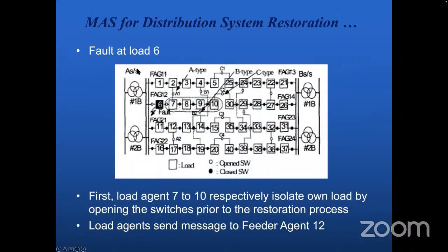So in this scenario, we have a fault at load 6. When we have a fault here, everything downstream is de-energized. So first, load agents 7 to 10 respectively isolate their own load by opening the switches prior to the restoration process.